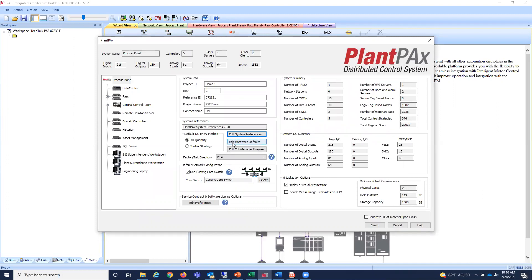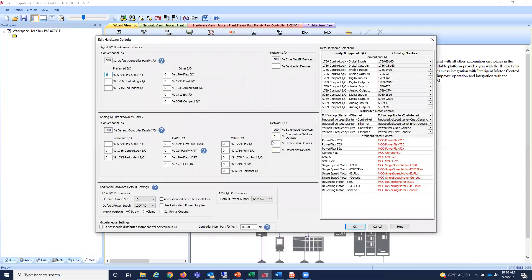Before you get started on a new system, PlantPAx has hardware defaults that let you set up what your default hardware would look like. For example, I can say 100% of my I/O is going to be the same family as my controller — I'm building everything with ControlLogix in this project. If I wanted HART I/O, I could select that as my default. If I wanted redundant power supplies, I just check the box and every I/O drop and controller will have them.